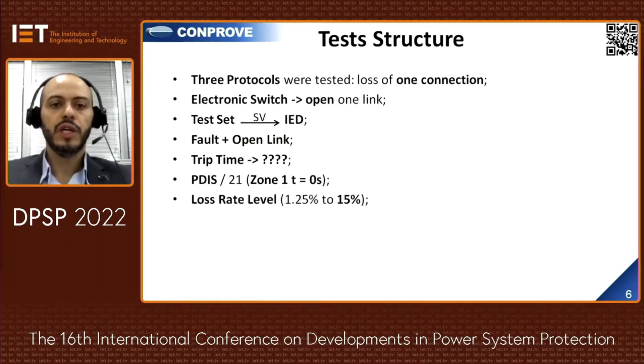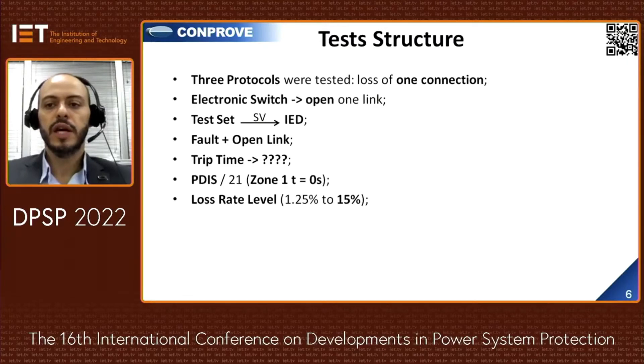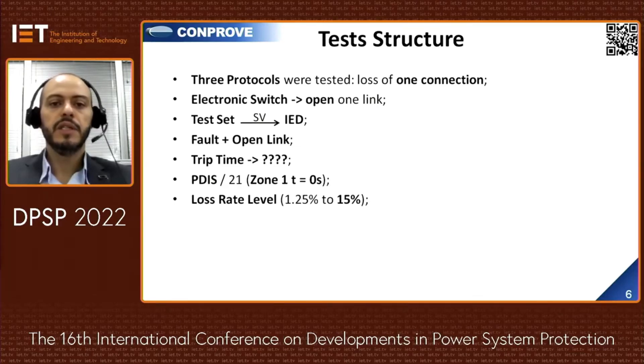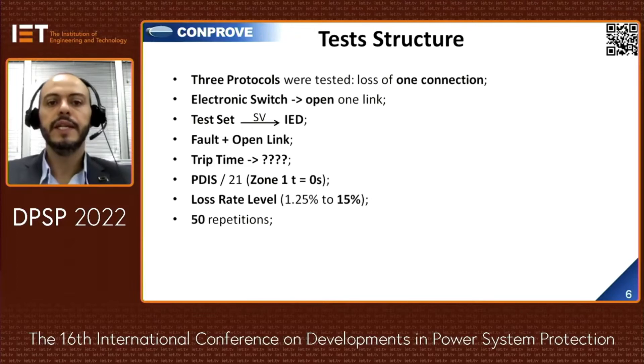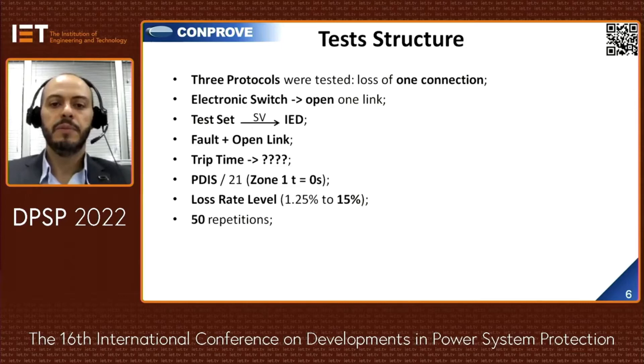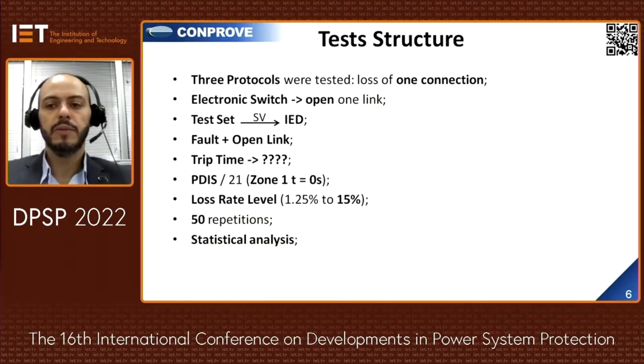The IED was tested with the distance protection function enabled. For this study case, faults were injected in Zone 1, which was parameterized with no time delay. The loss rate level parameter was set to 15% in the IED. The limit of the loss rate level is from 1.25% to 15%, indicating how many sampled value frames the IED can lose without blocking the protection function. In each case, the trip times were evaluated 50 times, and statistical analysis calculated minimum, average, maximum, and standard deviation.